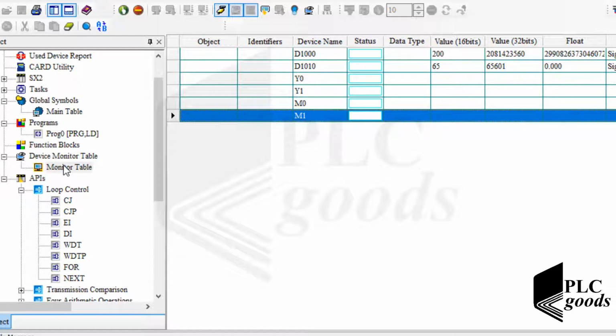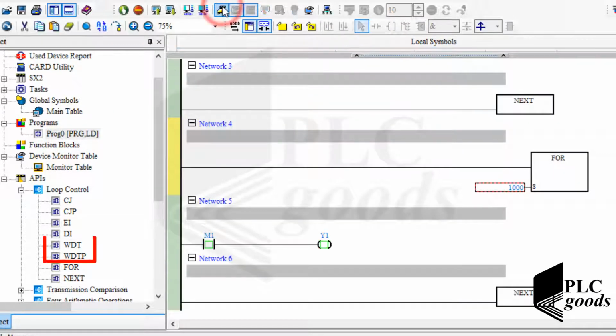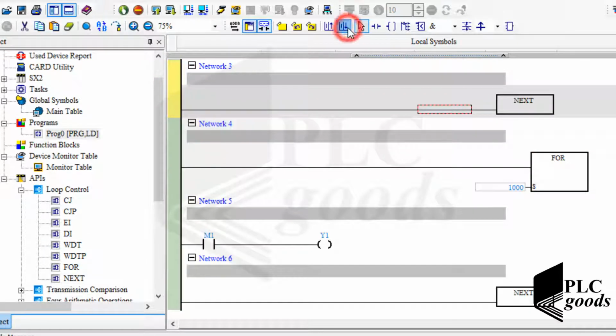If the scan time is too long, there are three ways to solve it. The best way is to modify the program, to decrease the scan time. Otherwise, we can change the stored number in this memory with a simple move instruction. Or inside the program, we can use WDT, Watchdog Timer instruction.